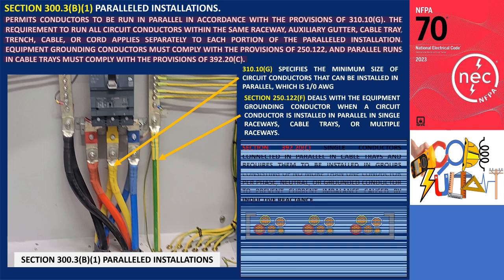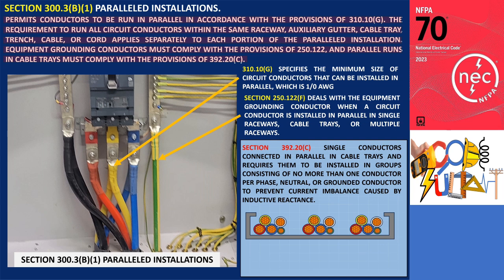Section 392.20.c addresses the installation of single conductors connected in parallel in cable trays and requires them to be installed in groups consisting of no more than one conductor per phase, neutral, or grounded conductor to prevent current imbalance caused by inductive reactance.